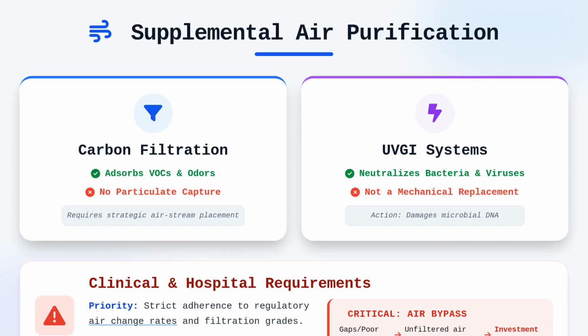Beyond mechanical filtration, we often encounter supplemental technologies like carbon filters and ultraviolet germicidal irradiation, known as UVGI. Carbon filters use the principle of adsorption to remove volatile organic compounds and odors, but they do not capture physical particulate matter and must be placed correctly in the airstream to be effective. UVGI systems are installed to neutralize airborne microorganisms, including bacteria and viruses, by damaging their DNA, but they are not a replacement for mechanical filtration.